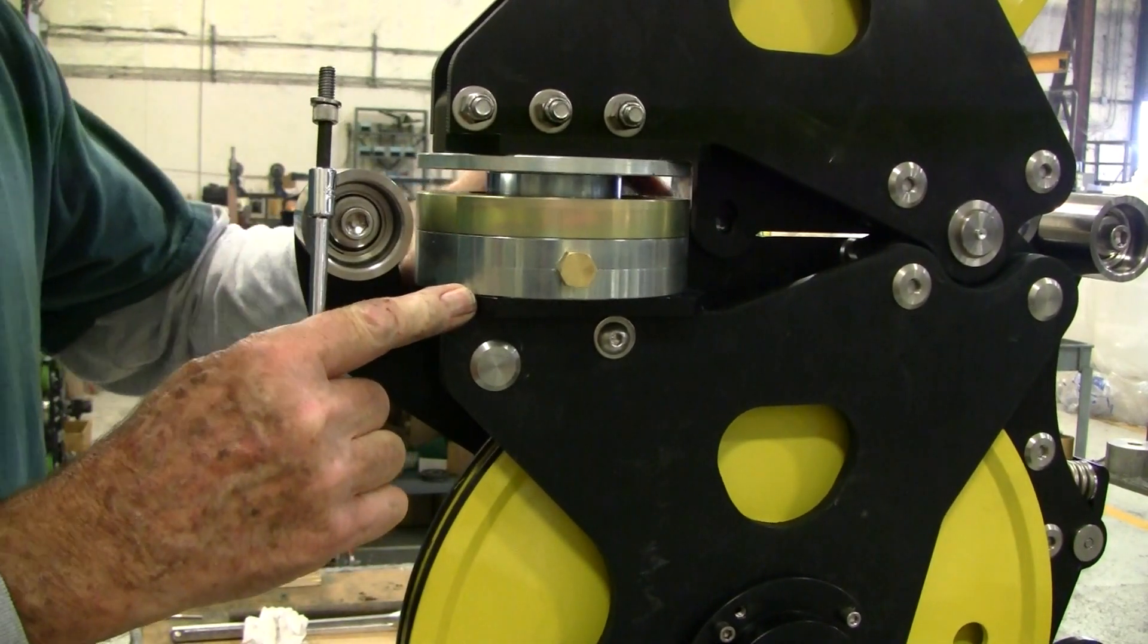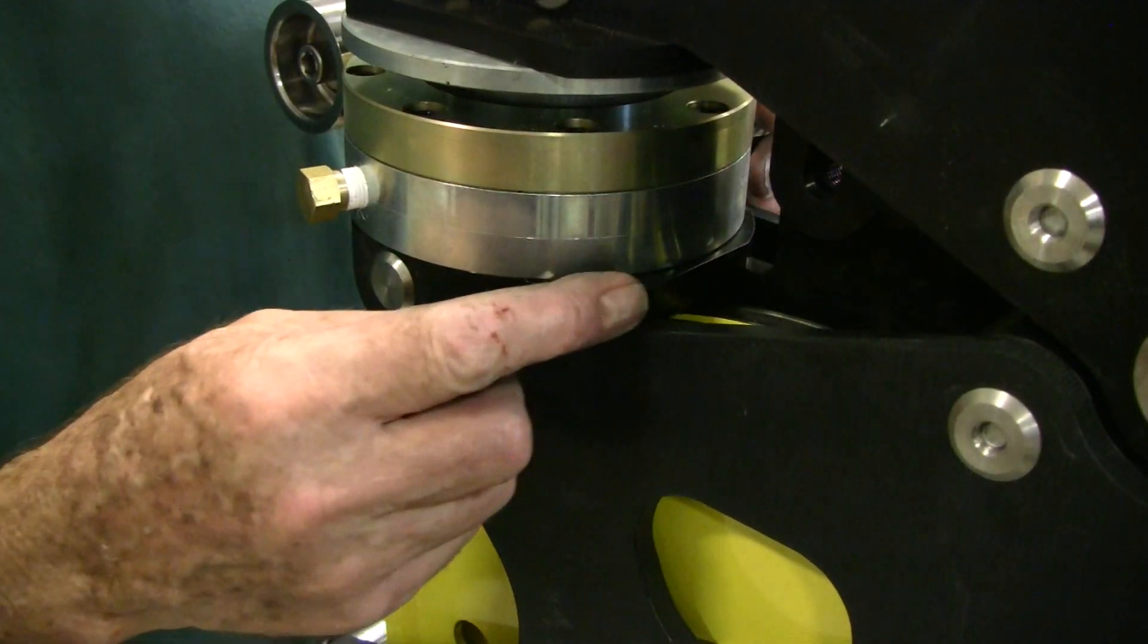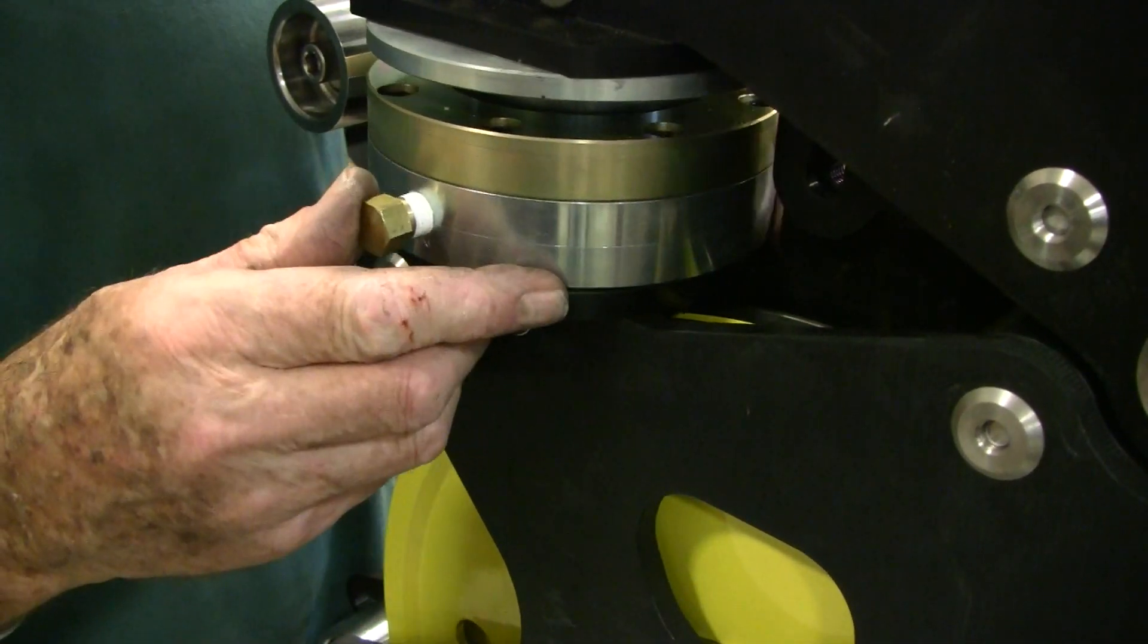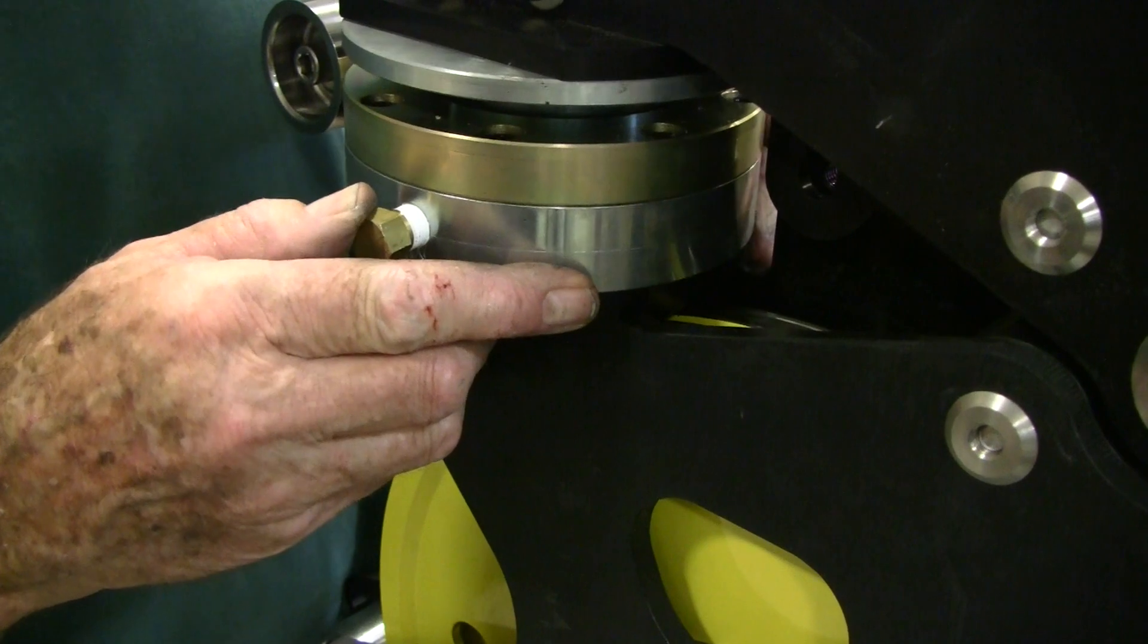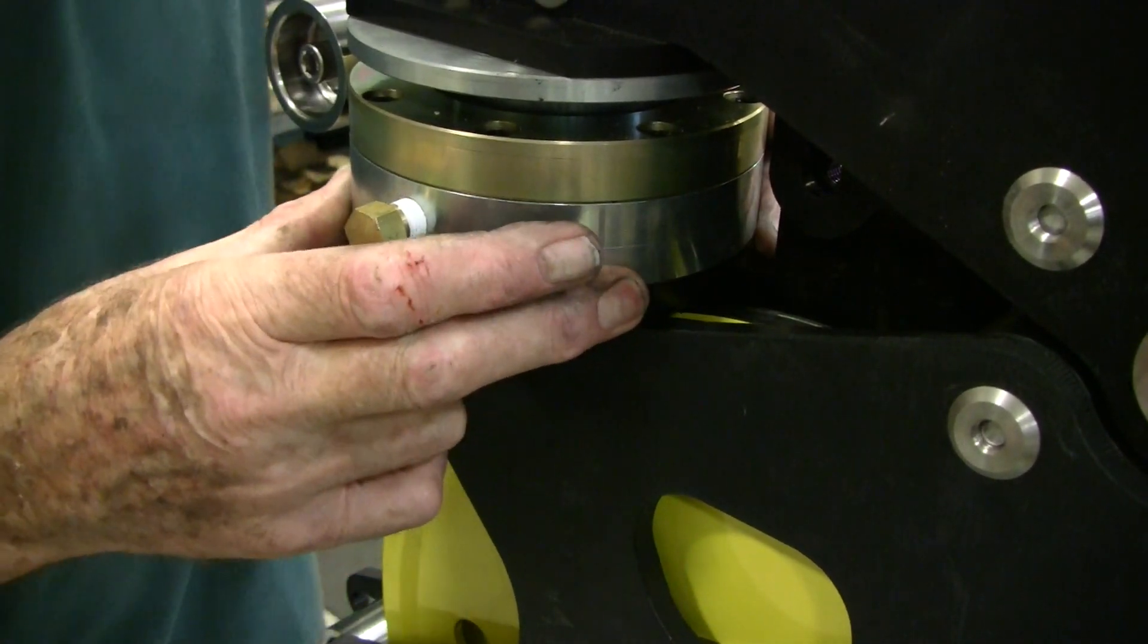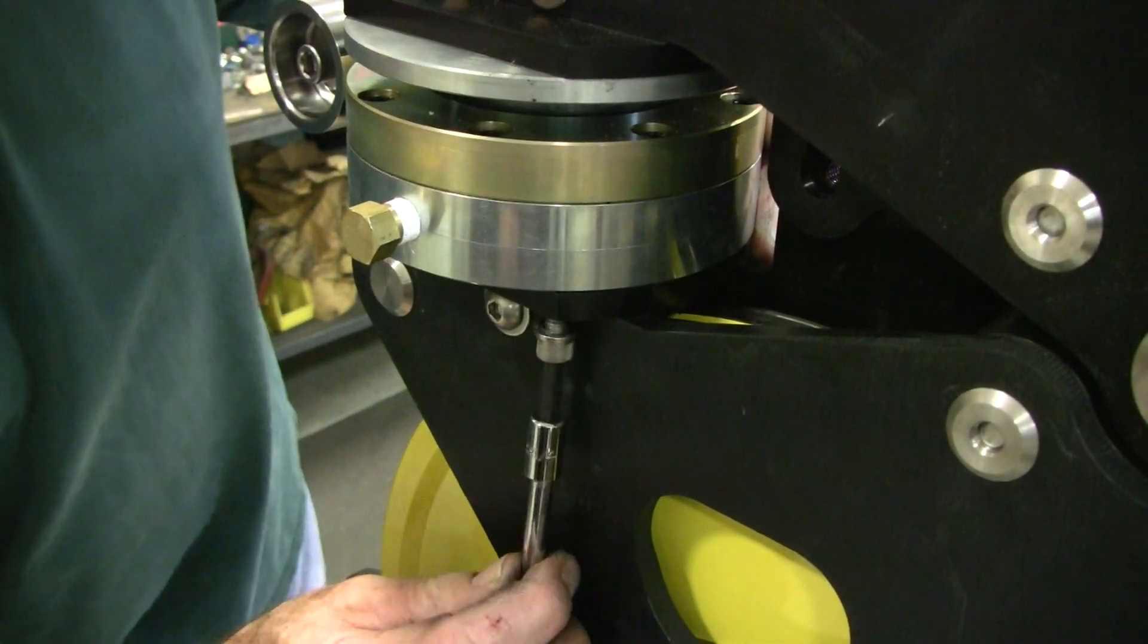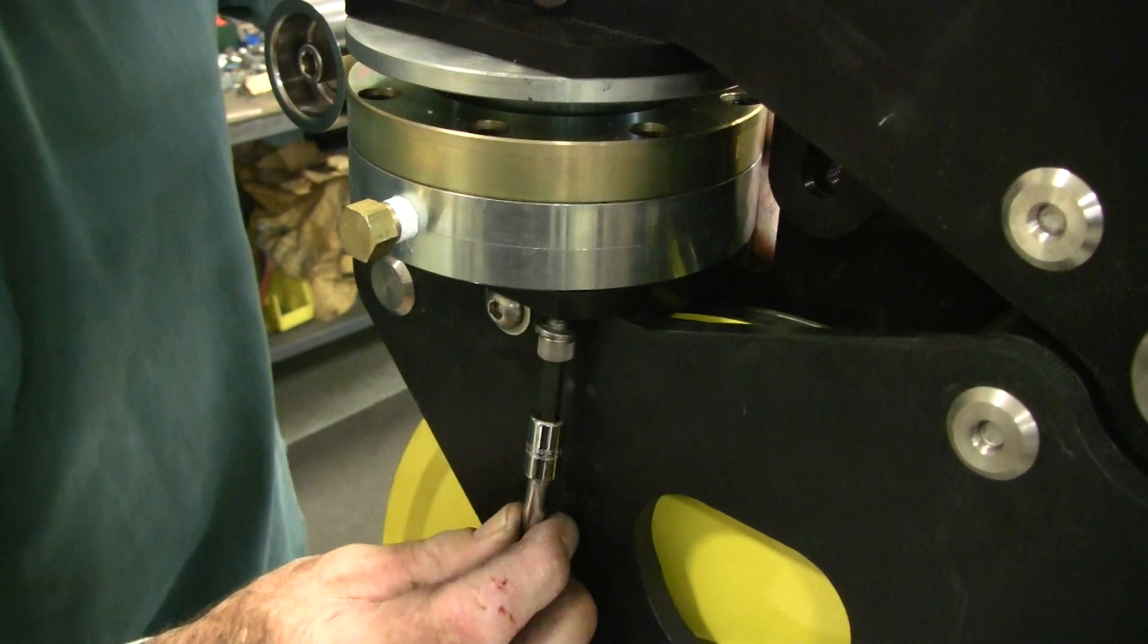Position the load cell so that the corners of the cell match up with the rounded corners of the mounting plate, and center the load cell as shown. Now install the two screws through the bottom of the mounting plate. Do not fully tighten them at this point.